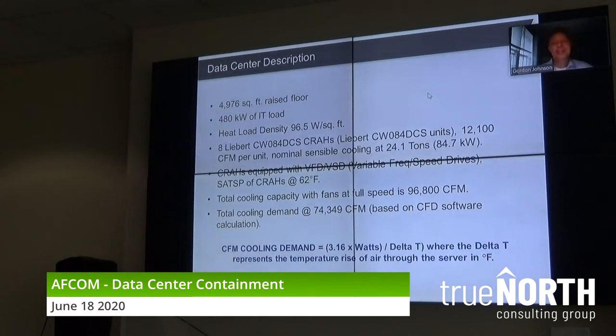So what does that mean? Well, you need to know, for instance, if you have a server, that delta T used to be 20 degrees 10 years ago. It's not 20 degrees today. It's 25 degrees, 30. The latest blade servers, it could be 40.